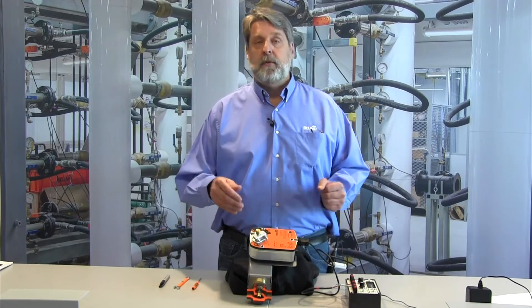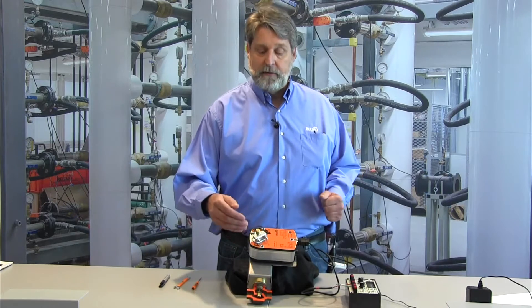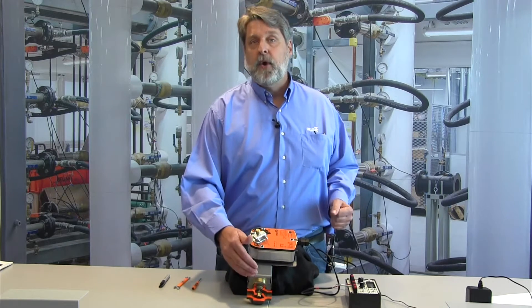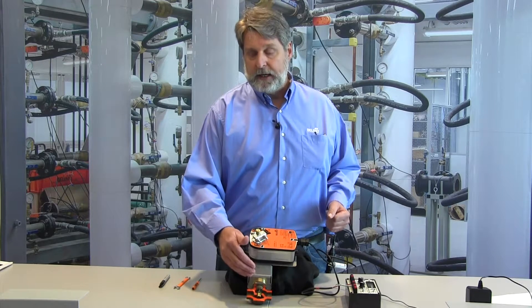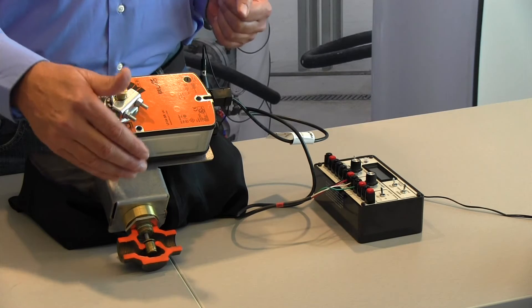What pre-tensioning does is it puts constant downward pressure on the globe valve seat so that you get less leakage. Keep in mind that a globe valve is never zero leakage, but by pre-tensioning you can reduce the amount of leakage that you get.